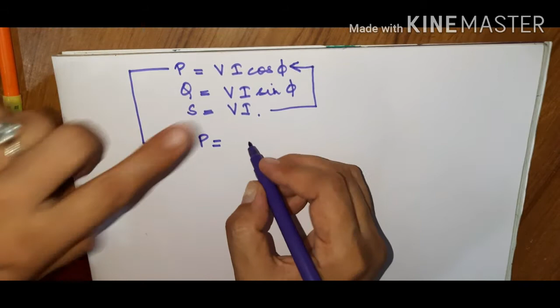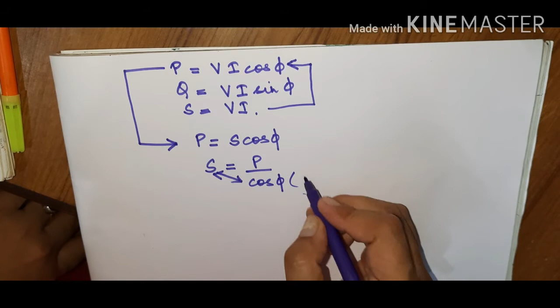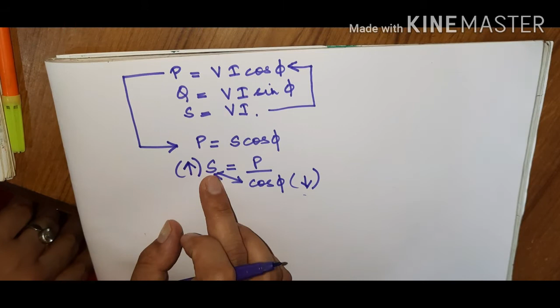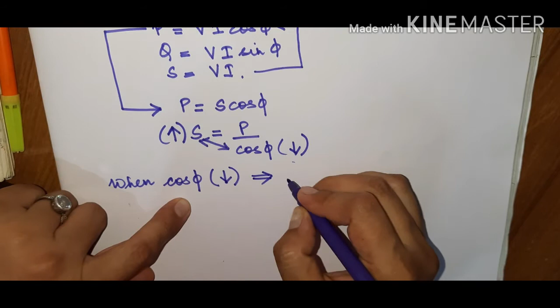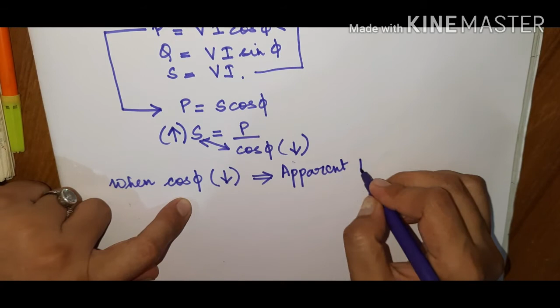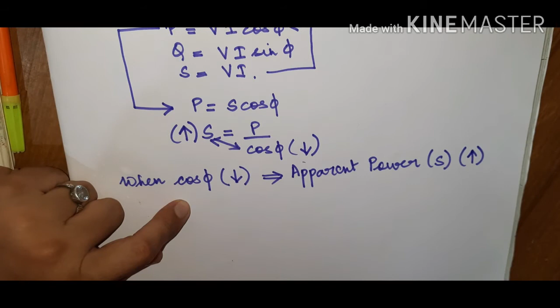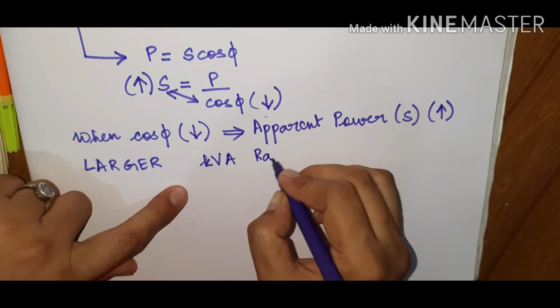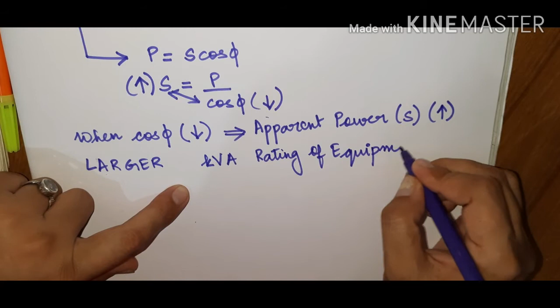The apparent power S is given by P divided by cos phi, so another inverse proportionality comes up. Whenever there is a low power factor, the kVA rating or apparent power increases. So when cos phi, the power factor, gets low, it causes the apparent power S to increase, and when it increases, you have to provide a larger kVA rating of equipment.